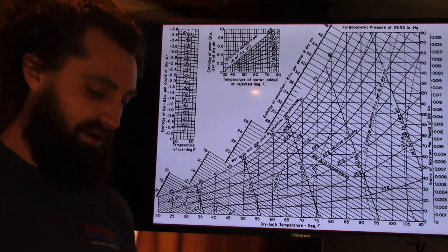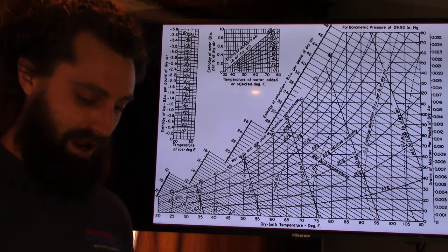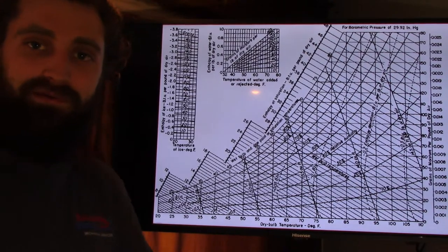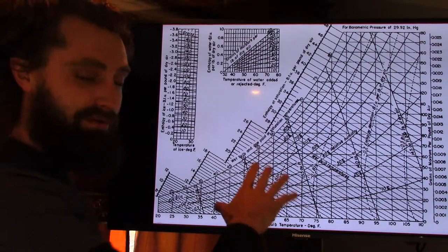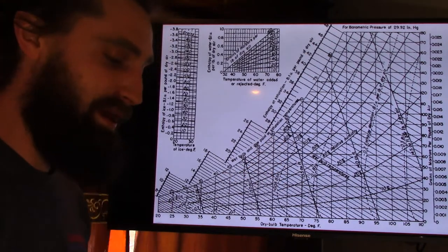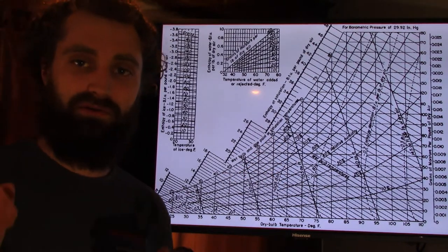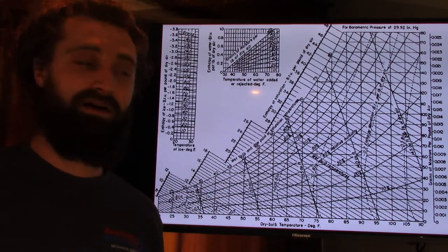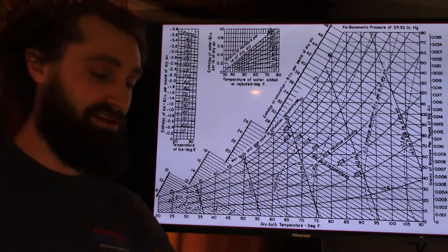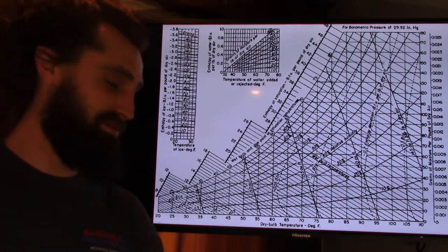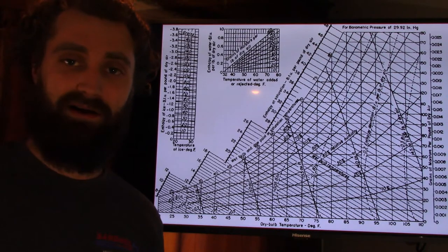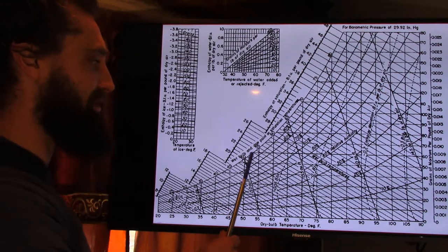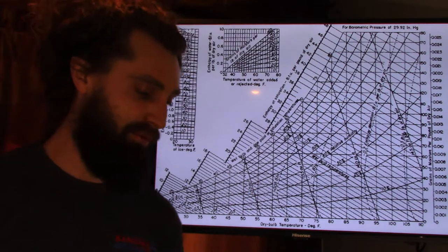And I remember the very first time that I got a hold of a psychrometer. I felt like I was big man on campus. I had never even looked at one of these charts or taken a class on it. I plugged into a return, and I was like, oh, this is really neat. I plugged into a supply. I said, whoa, something is wrong here. It's just dumping humidity into the air. It's just spraying the supply duct with water. And it was a concern for me because I didn't realize how that worked.